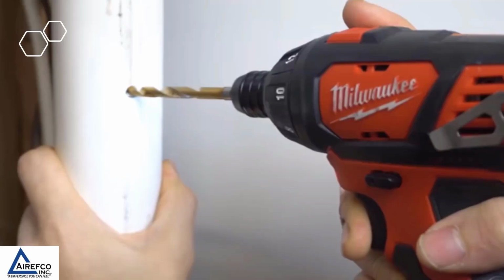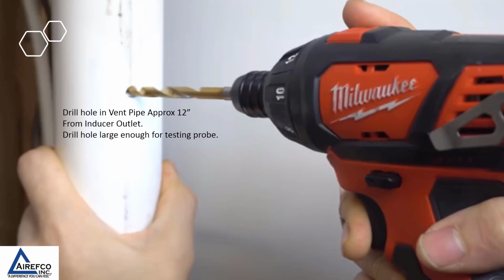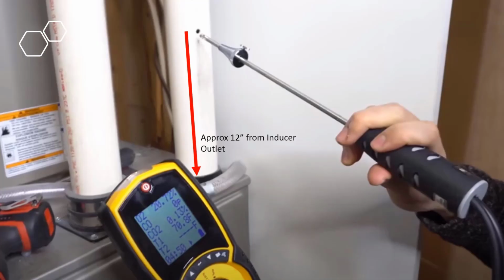In order to take a CO reading on a gas furnace, you need to drill a hole in the vent pipe approximately 12 inches from the inducer outlet. Drill the hole large enough for the testing probe that you are using to insert inside it. Once you have the hole drilled in the vent pipe, insert the CO sensing probe into the hole approximately 12 inches from the inducer outlet.